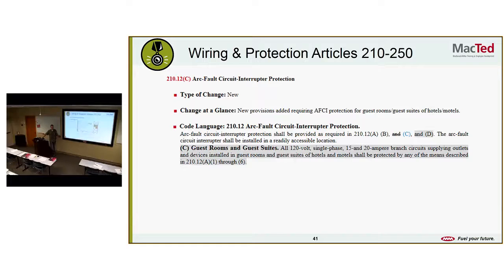Arc fault. Anybody dealt with arc fault protection? I've just gone through this, doing a kitchen remodel. Anybody else have any nuisance trips with these arc fault things? They're a pain in the ass. Yes, they are. The breakers themselves, they make all kinds of money on it. I bet McDonald Miller does, yeah. Man, they're a nuisance. They're supposed to look for arcs, but I think motor loads are really hard on them. Yeah, like the vacuum, fridge, garbage disposal, big mixers. When you plug something in and it makes that little arc in the receptacle, that'll trip them. Yeah, super annoying. I found that too. I'm glad it's not just me.